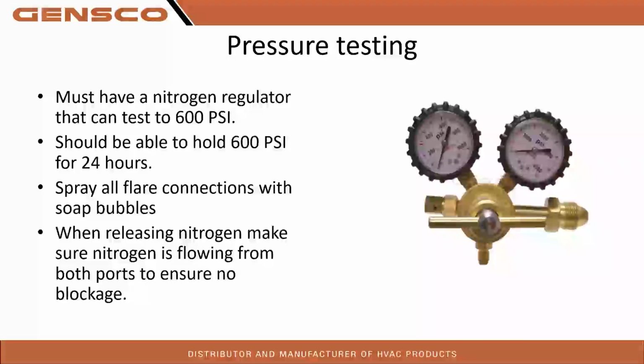Yeah, very good point. So I think a lot of the regulators we're selling through Gensco I want to say are 800 PSI rated. So Chris does bring up a really good point. Yeah, make sure that your regulator can actually test higher than what our testing pressure should be. And keep in mind when you guys are doing pressure tests, we're trying to test above our operating pressures. So we can get up into 500 PSI under certain circumstances pretty easily. So you guys want to make sure that you're pumping up well above that. That way we're actually ensuring we're holding that pressure.